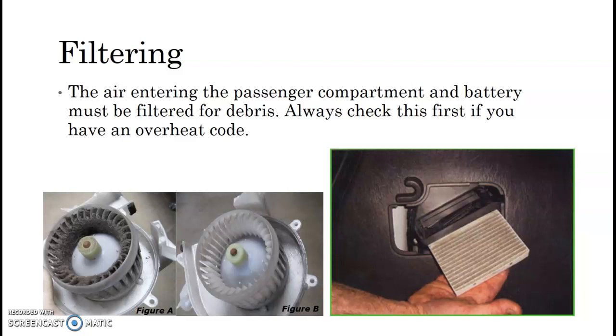Just like a common overheat failure of a liquid-cooled battery is going to be a bad electric water pump, it could also be a bad electric valve, the chiller system, or low coolant. Those are the things you're looking at for diagnosing an overheat code on a liquid-cooled battery system.